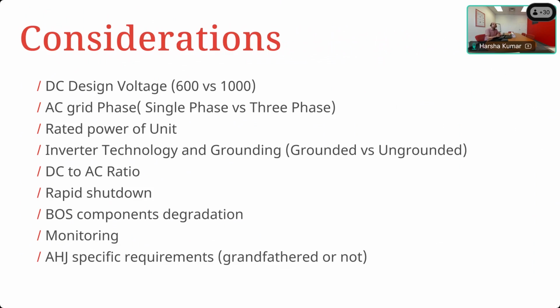This is basically transformer-based versus transformer-less. A transformer-based inverter will have one pole of the PV array tied to ground inside the inverter. So if you did have a failure of insulation due to degradation, it isn't a big problem because you're already bonded to ground inside the inverter.